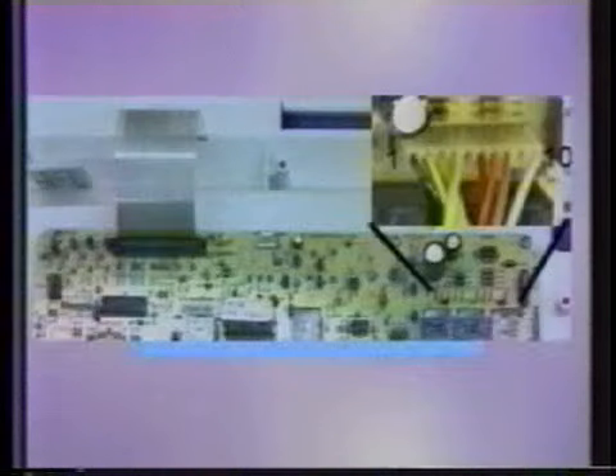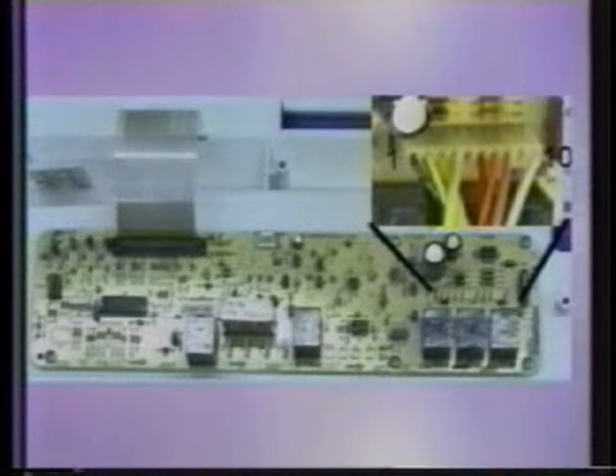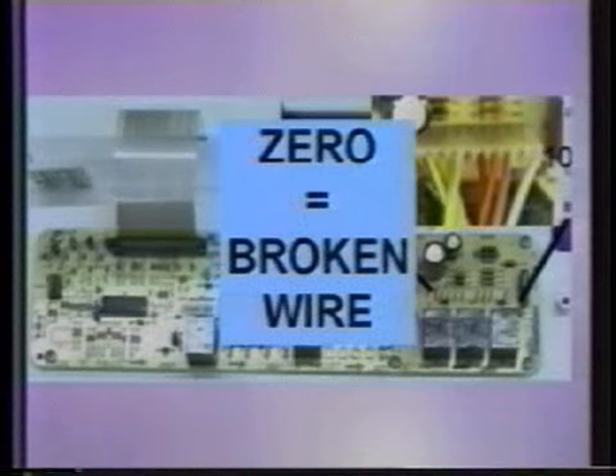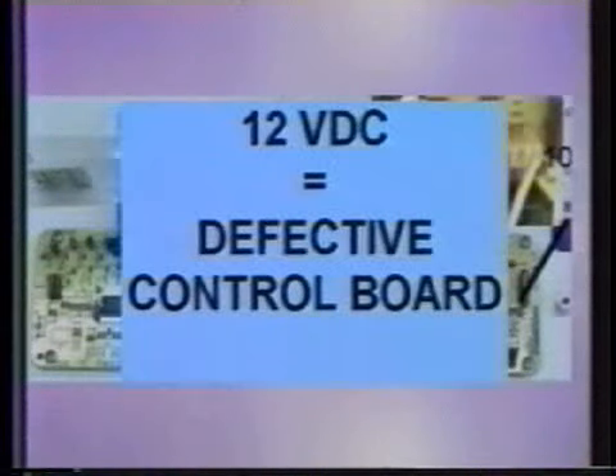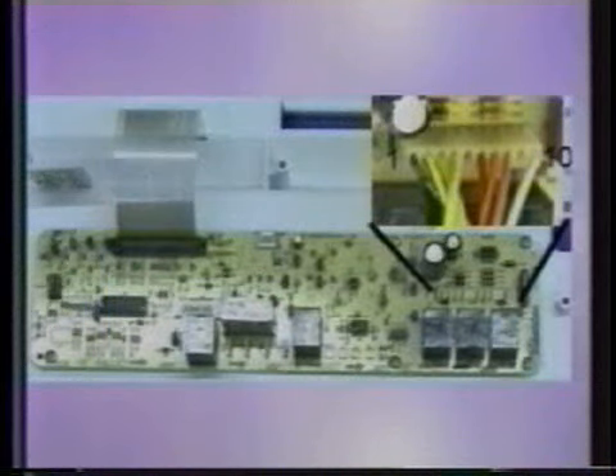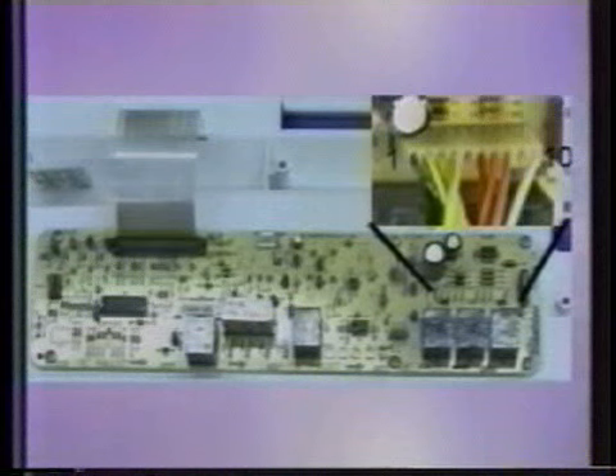If I get 12 volts out of the transformer, my next stop is the back of the control board. And here I want to measure the voltage drop between pins 1 and 2 of the 10-pin plug. If I have 0 volts here, this indicates to me that I have a broken wire between my transformer and the control board. If I have 12 volts, this should indicate a bad control board, but let's make one quick check just to double check ourselves. The quick check would be to measure between pins 3 and 4 of the 10-pin plug, and here is the 5 volts DC output to the thermistor. If I get 5 volts from here, this would indicate to me that I had a broken wire going to my thermistor and that the test had given me the wrong direction.